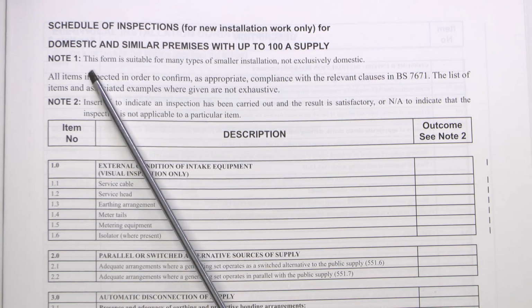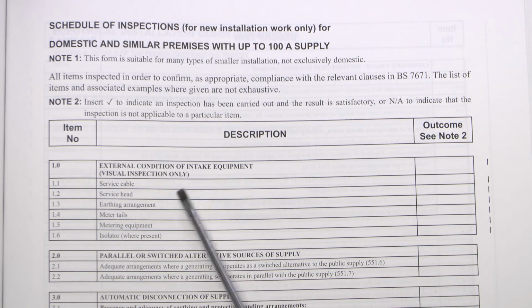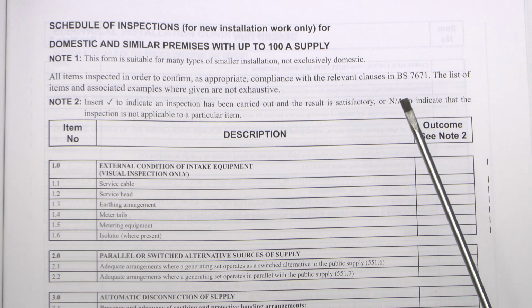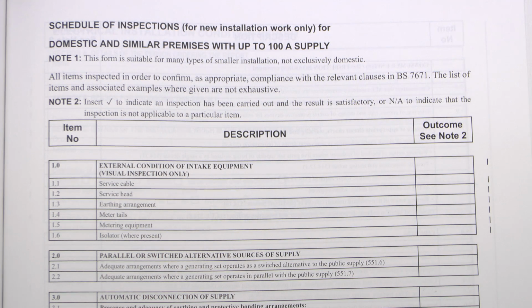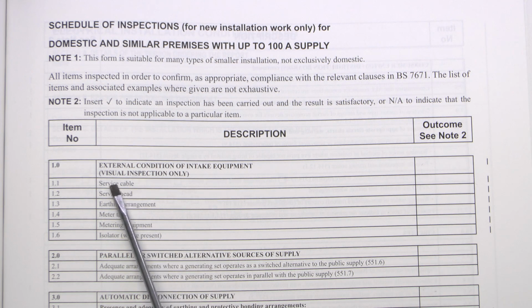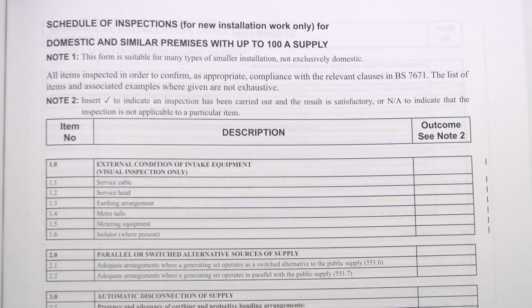So, schedule of inspections, and again this is the part that goes with either of the two previous documents there, either the certificate or the inspection report. The main one here is on section 1 or item 1, external condition of intake equipment. It now states visual inspection only, and that's for things like the service cable, metering and so on. That's not really a change, because clearly it was pretty much going to be visual only anyhow, because there's nothing that you can test on those, but just highlighted up as visual inspection only.